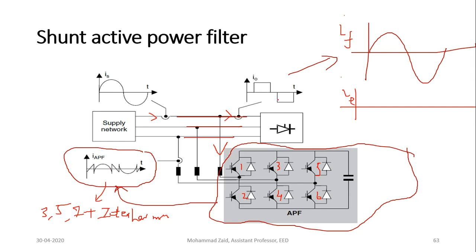Because you see, the harmonic load is like this. It is just like your square wave inverter waveform, but the harmonic components are very, very difficult. So the passive filters will not work here, because passive filters will not be able to eliminate all the frequency components which are available. You would need a passive filter for every other harmonic elimination. It will reduce the dominant part but not every part of the harmonics. So that's why you need to control this.